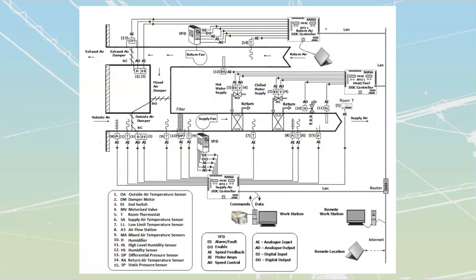And altogether, we'll have a system that is oftentimes referred to as our DDC system, which is a direct digital control. Direct digital control is similar to what you may have heard before referred to as a PLC. PLC is a programmable logic controller, and it's basically an open source type of component. It's not actually open source, but it's just a bunch of inputs and outputs, and you choose what exactly you want any of those inputs and outputs to do. And you create your own screens and GUIs, the graphical user interface, all that other stuff. You do that inside of a PLC.